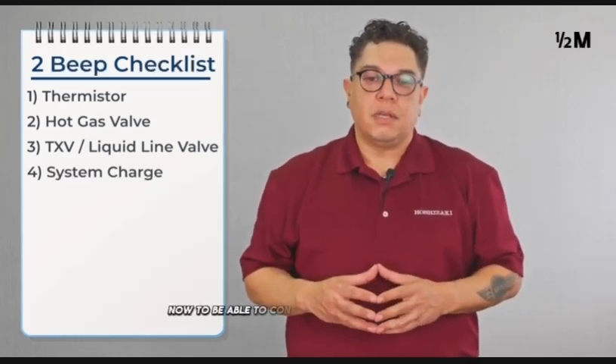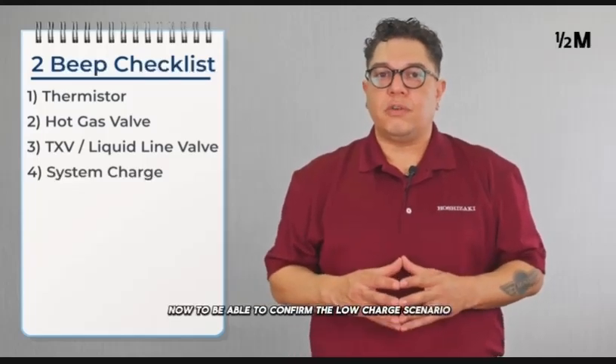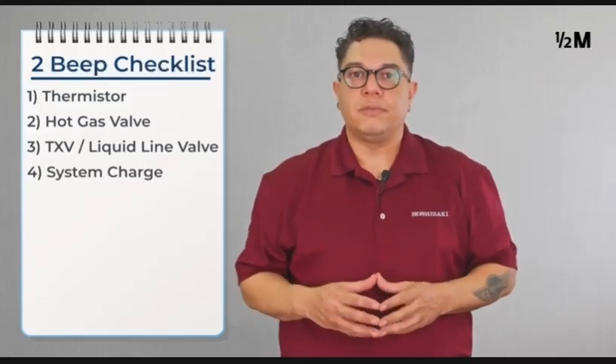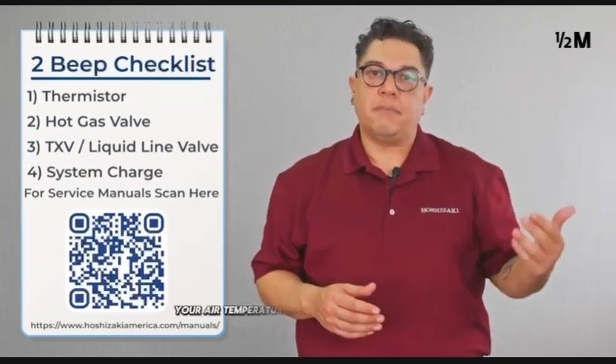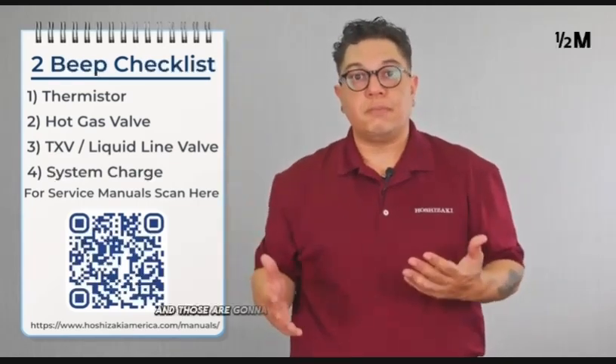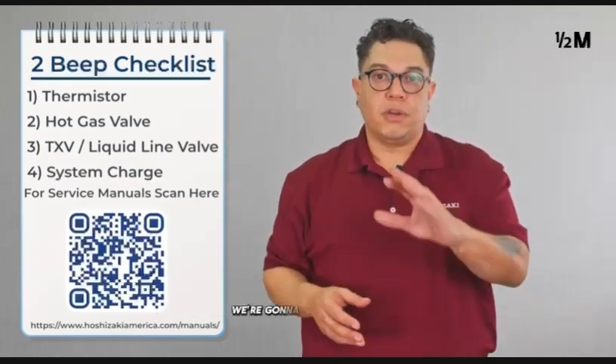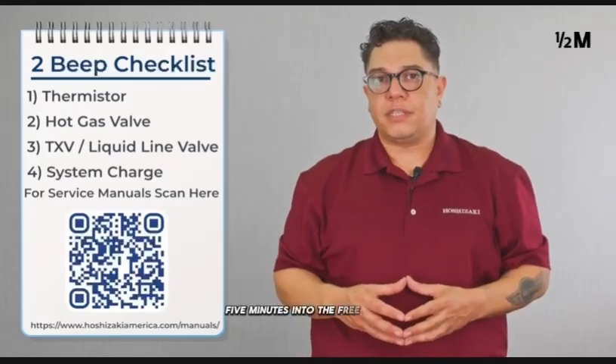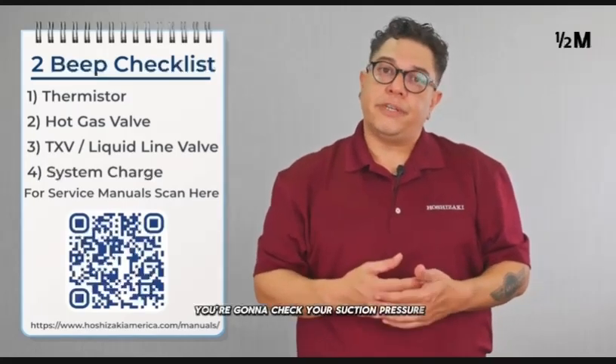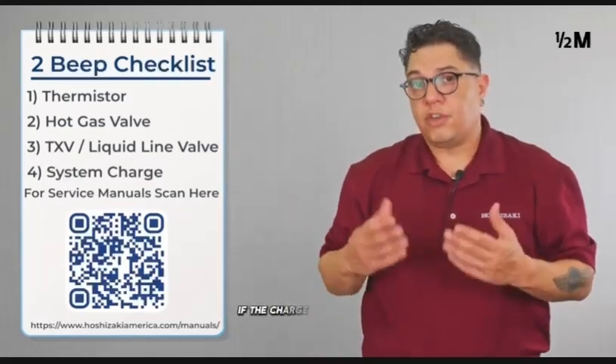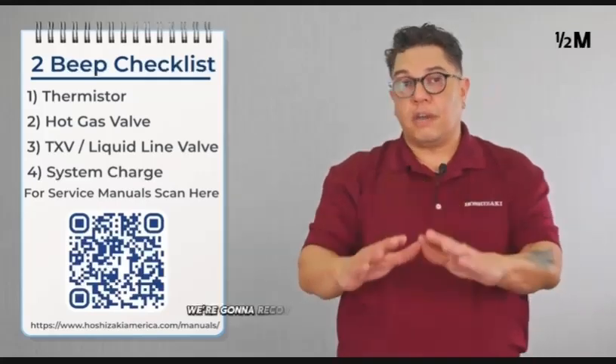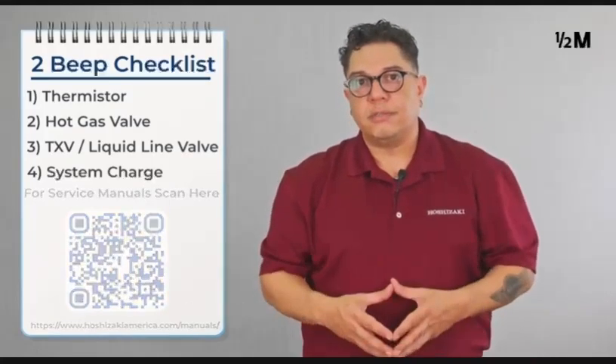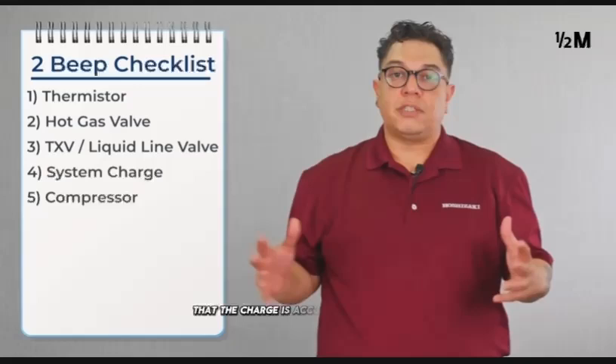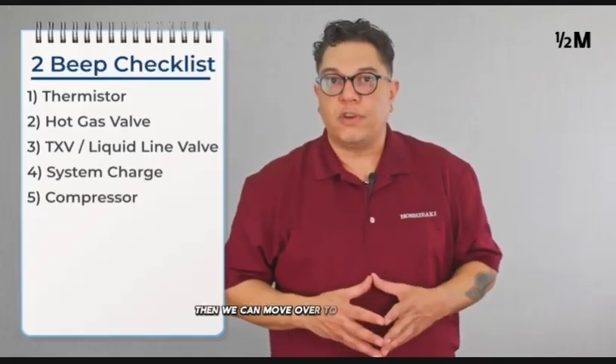Now, to be able to confirm the low charge scenario, we need to reference the service manual. In the service manual, there's a chart. You're going to line up your air temperature and your water temperature, and those are going to be your pressures for your machine. We're going to check pressures 5 minutes into the freeze cycle. You're going to check your suction pressure and your head pressure. If the charge is inaccurate, we're going to recover and weigh in the charge.